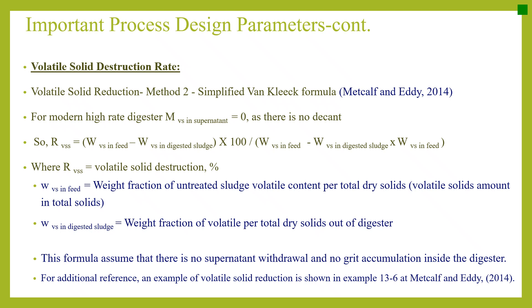Here RvSS is volatile solid destruction percentage, WvSS in feed is the weight fraction of untreated sludge volatile content per total dry solids, and WvSS in digested sludge is the weight fraction of volatile per total dry solids out of the digester. This formula assumes no supernatant withdrawal and no grit accumulation inside the digester. Example 13.6 in Metcalf and Eddy, 5th edition provides a worked example of volatile solid reduction.